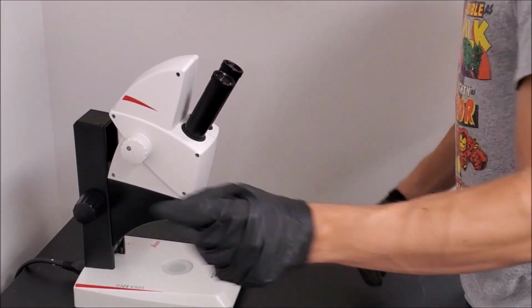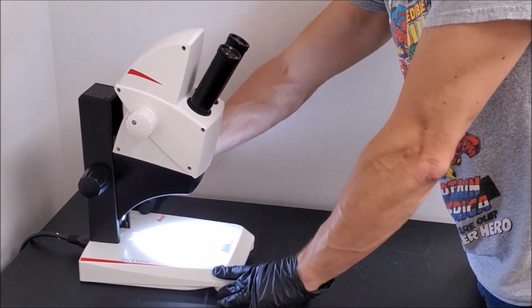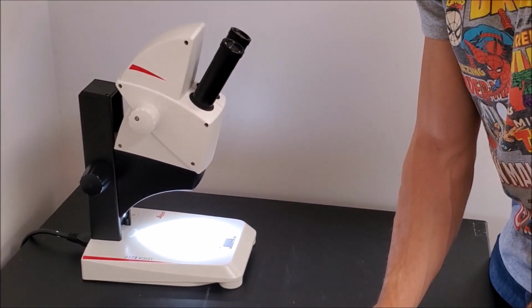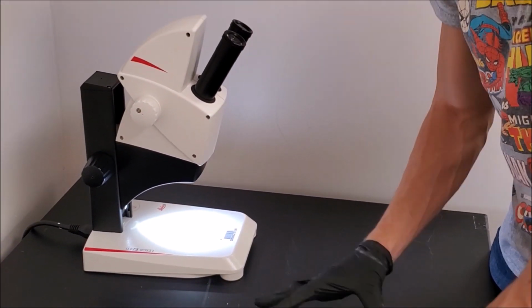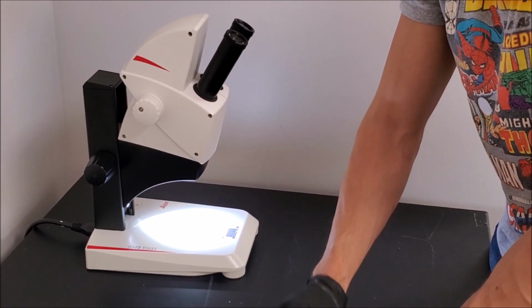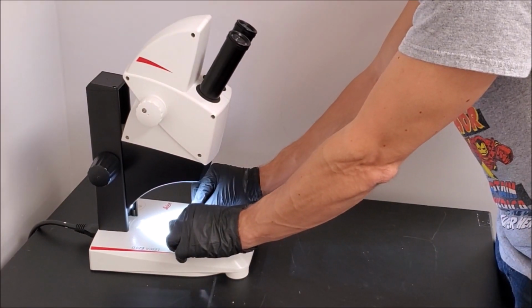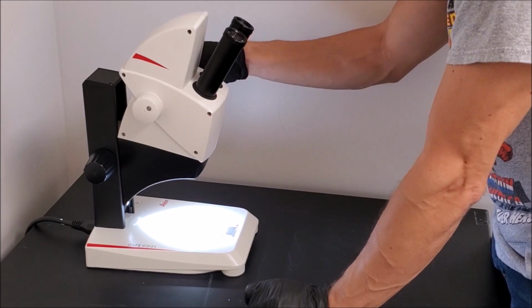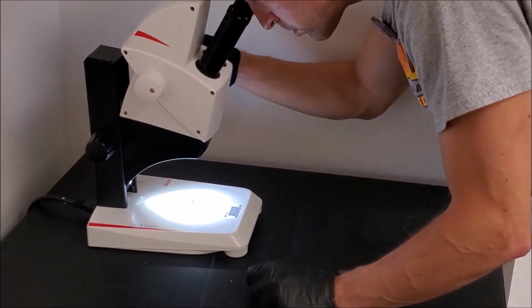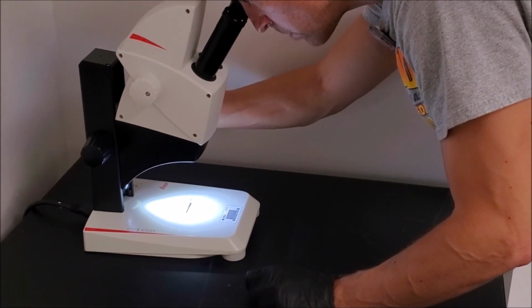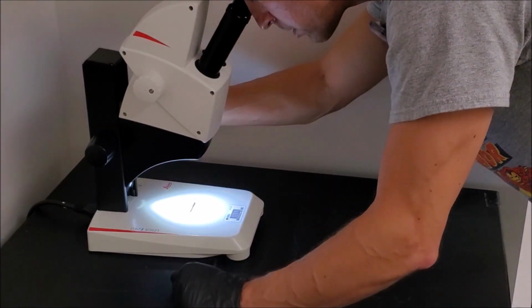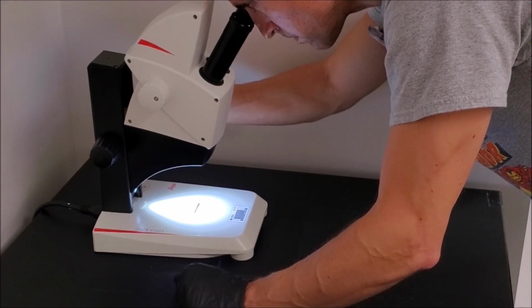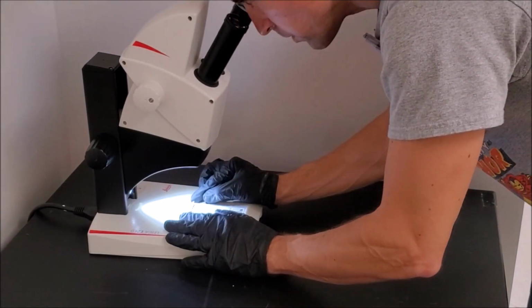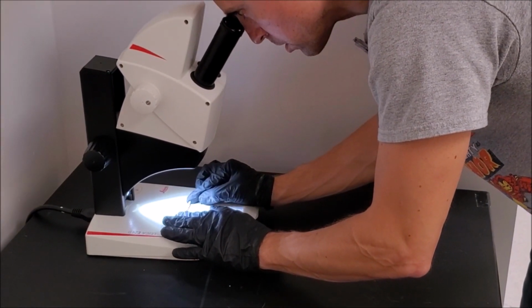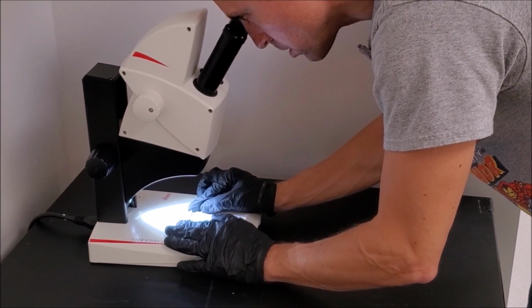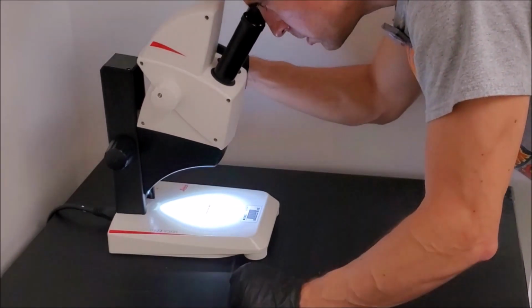Use an optical microscope to verify that the grid is not bent. Place the grid holder onto the stage of the microscope. Orient the grid holder such that you are facing the grid edge on. Then focus on the edge of the grid to verify that it is straight. If the grid appears bent, it should be discarded, a new grid loaded, and then again verified that it is straight before proceeding.